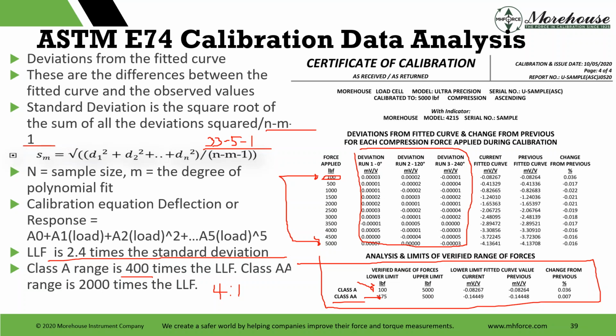So we take Class AA times 2,000, and guess what that gives us? If we calibrate another instrument to Class A, that's going to build in a 5-to-1 scenario where we're going to be 5 times better at that first force point than what we're calibrating. Really, really cool stuff here.